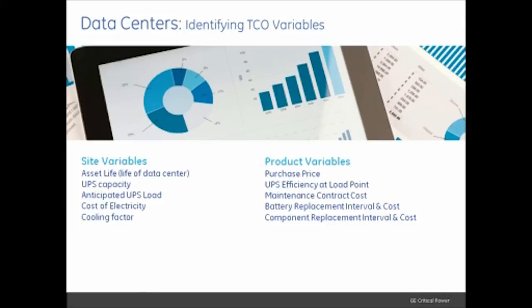Now, to properly do a TCO analysis, you need to understand what all the variables are. Some are for the site, some for the actual product, and TCOs can also include financing costs, leasing costs, even escalation factors for what power prices might do, or you could change your load over time. The TCO can be evaluated in straight line dollars, as we're doing here, or net present value, for which you'd have to add the cost of capital. One of the more important site variables is the cooling factor, calculated as the kW required to power the mechanical cooling divided by the kW of heat removed.